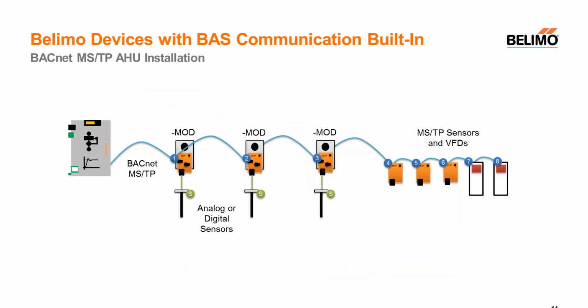Now you just run a bus connecting all of your devices together. Sensors can be connected to local devices like the actuators instead of home runs back to the digital controller. And where it makes sense, you can use communicating sensors. We have a line of sensors that talk on Modbus and BACnet as well, instead of just actuators. And most VFDs today include BACnet MSTP communication. So basically you can do an entire air handler using bus devices.